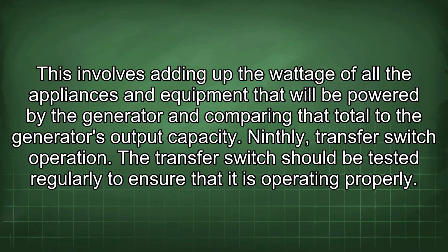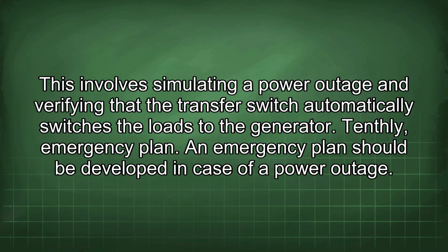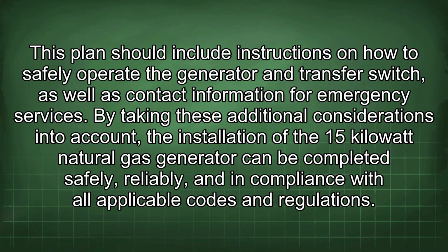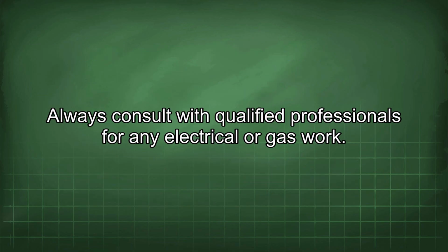Ninthly, transfer switch operation. The transfer switch should be tested regularly to ensure that it is operating properly. This involves simulating a power outage and verifying that the transfer switch automatically switches the loads to the generator. Tenthly, emergency plan. An emergency plan should be developed in case of a power outage. This plan should include instructions on how to safely operate the generator and transfer switch, as well as contact information for emergency services. By taking these additional considerations into account, the installation of the 15 kilowatt natural gas generator can be completed safely, reliably, and in compliance with all applicable codes and regulations. Always consult with qualified professionals for any electrical or gas work.